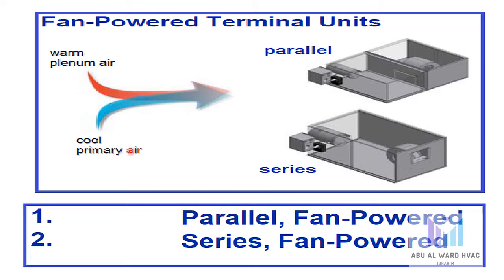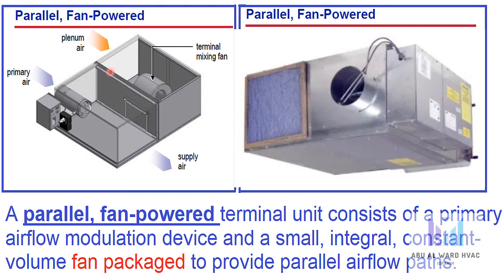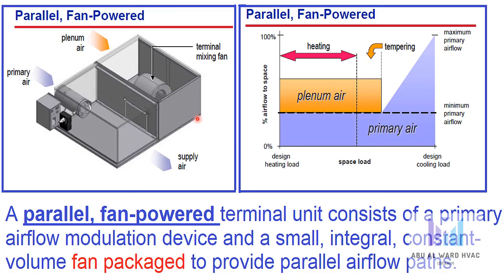Another method that a single duct VAV terminal unit can employ to heat a space is to mix warm plenum air with cool primary air. Because this method uses a small fan to draw warm air from the plenum and mix it with the primary air, they are called fan powered terminal units. They come in two configurations: parallel and series. A parallel fan powered terminal unit consists of a primary airflow modulation device and a small integral constant volume fan packaged to provide parallel airflow paths. In the cooling mode, the unit is controlled in the same manner as the cooling only unit — primary airflow is reduced as the cooling load in the space decreases.